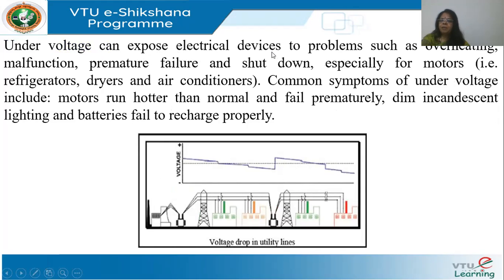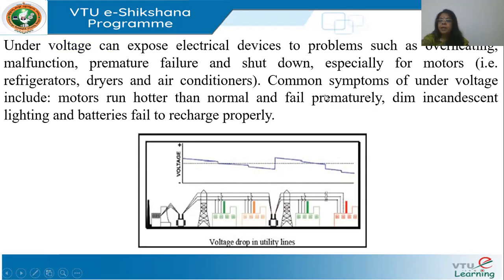Under voltage can expose electrical devices to overheating — if it's a constant power load, it may draw more current to maintain the same power (P is proportional to VI). Motors may malfunction, run hotter than normal, or fail prematurely. Incandescent bulbs will dim, and fluorescent bulbs may not come on at all. Capacitor banks can partially compensate, but voltage may still fall at long distances.